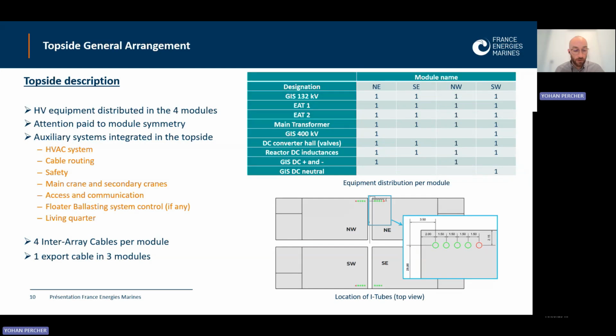On the bottom right figure, you can see the location of the I-tubes, the vertical tubes that receive the electrical cables. 16 of them, shown with green circles, are for the inter-array cables coming from the wind turbines, and 3, shown in red, are the export cables: one for the positive pole, one for the negative pole, and one for the neutral, going to shore.